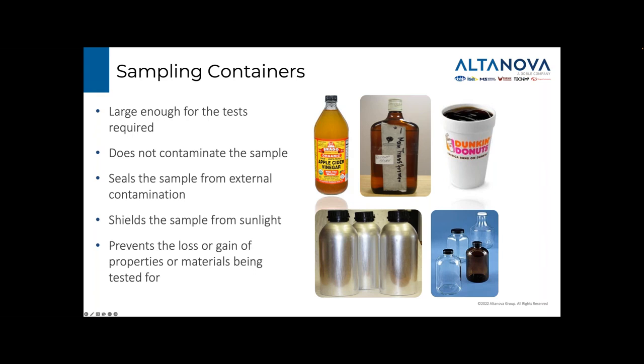If you're taking DGA samples, then the most representative data will come from the use of a glass syringe. All other tests can be done from bottles like the ones in the picture on the bottom line. Because aluminium can be filled to the brim without breaking in transit, they also retain quite good DGA properties, but the sampling process itself, being open to the atmosphere, means several gases like hydrogen and oxygen will never be representative of what's actually inside the asset.